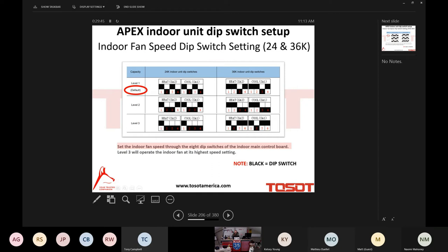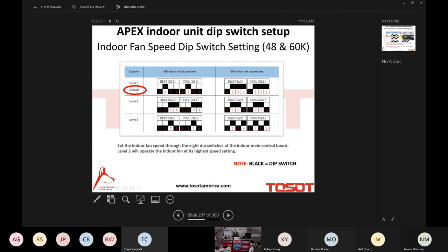What you're looking at here is for the 2-ton, for the 3-ton, levels 1, 2, and 3, and for the 4-ton, and for the 5-ton, levels 1, 2, and 3. Now, the black is the dip switch. Again, it's something that initially and still remains very confusing and will be for your customers, quite frankly. We're working on trying to make this a little easier to understand at first glance. At first glance, it's not intuitive, right? It's very difficult to see what Tosot is trying to tell us here. What's the dip switch and what isn't?